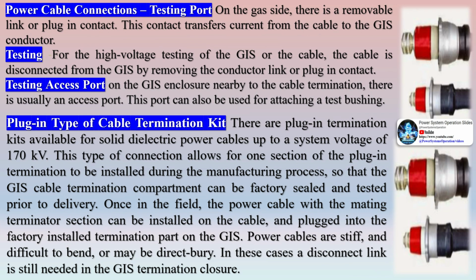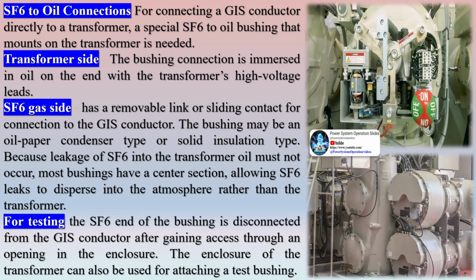Power cable connections. Testing port: on the gas side, there is a removable link or plug-in contact. This contact transfers current from the cable to the GIS conductor. Testing: for the high voltage testing of the GIS or the cable, it is disconnected from the GIS by removing the conductor link or plug-in contact. Testing access port: on the GIS enclosure nearby to the cable termination, there is usually an access port. This port can also be used for attaching a test bushing.